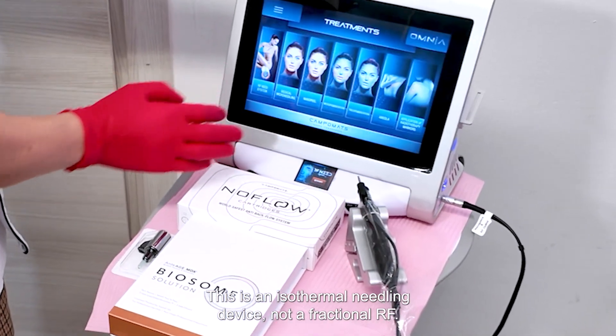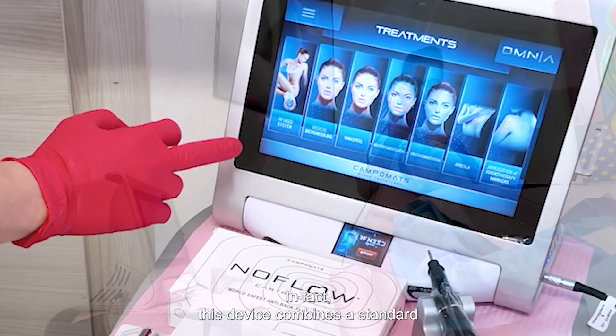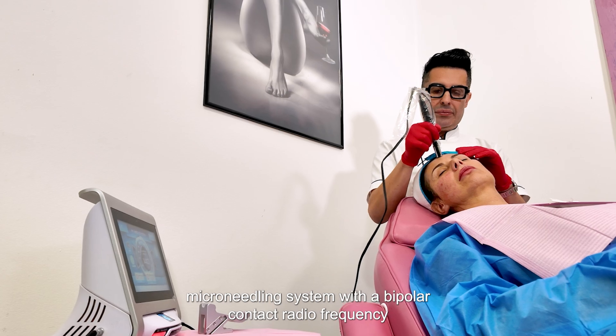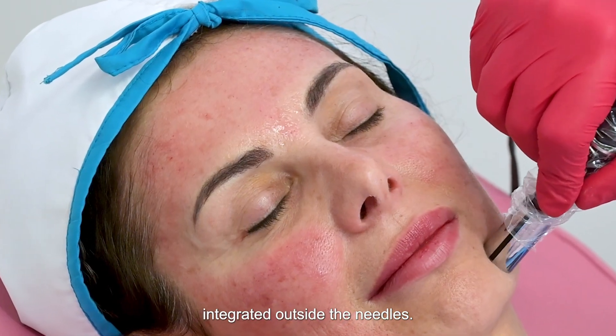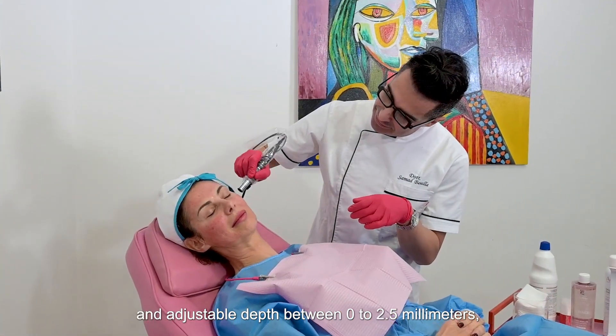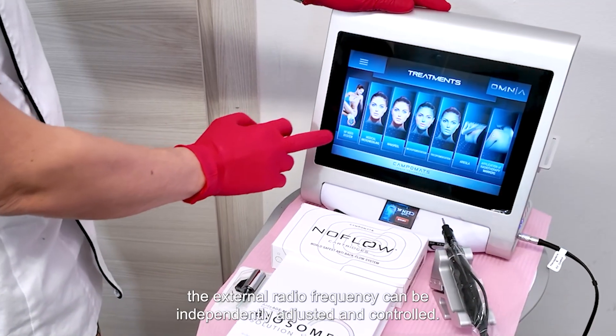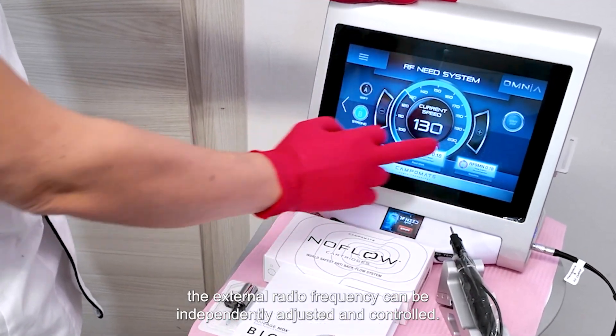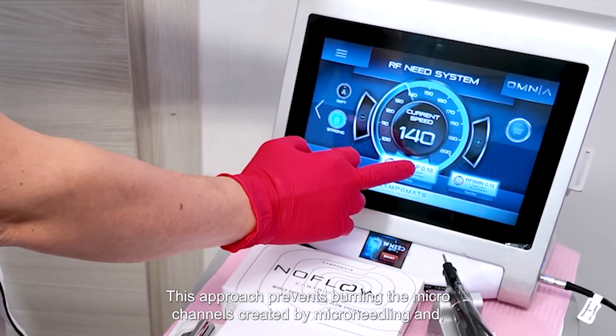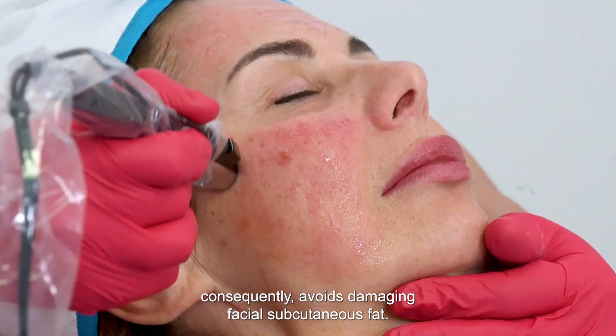This is an isothermal needling device, not a fractional RF. In fact, this device combines a standard microneedling system with a bipolar contact radiofrequency integrated outside the needles. This allows working with the microneedling cartridge at a variable and adjustable depth between 0 to 2.5 millimeters. With the RF NEED system, the external radiofrequency can be independently adjusted and controlled. This approach prevents burning the microchannels created by microneedling and consequently avoids damaging facial subcutaneous fat.